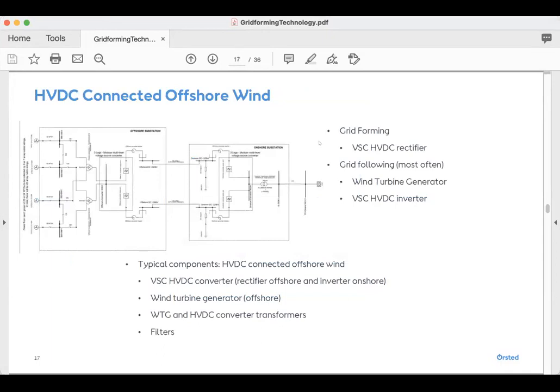For HVDC connected offshore wind, typically we have a voltage source converter HVDC system. The rectifier is always at the offshore end, and the inverter is onshore. The rectifier is the one that has grid forming capability, and not necessarily any kind of inertial response capability. It just has basic grid forming capability in most designs. The turbine itself and the HVDC inverter on the onshore end are always grid following. So there's a little bit of nuance on the onshore end, where we cannot expect the VSC HVDC to have grid forming capability. And again, the standard components would be filters that we always use and a converter transformer for isolation.